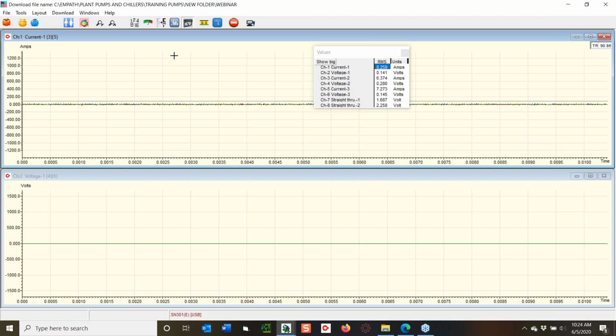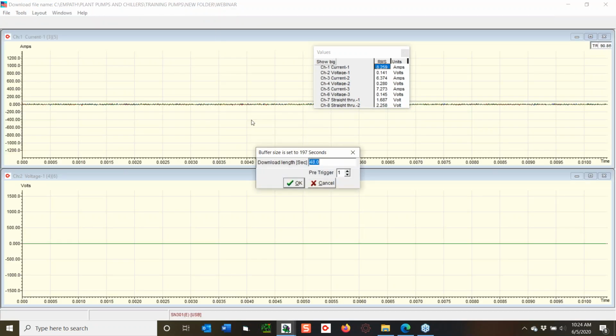Okay, so the next thing I want to do is click my download, and this will allow me to set a length of time that I'm going to collect data. So when does this come in handy? I had a DC machine, a very large DC machine, and we knew that it had 11 passes on this particular application. It was a roughing mill. So we figured out it was about 240 seconds, so I set it for 300 seconds, 5 minutes, and just let it run. So it would start and then it just ran for that length of time, got all the data.